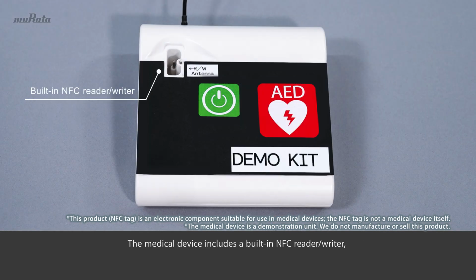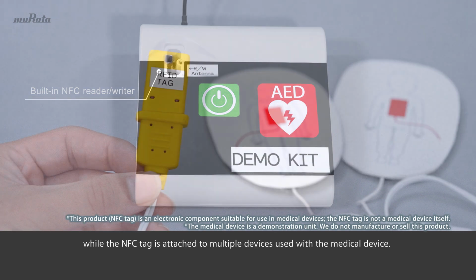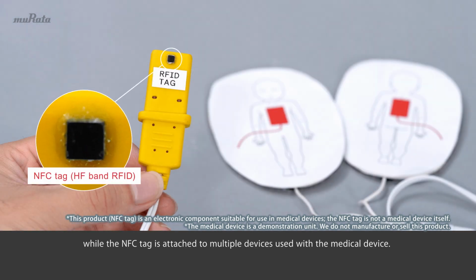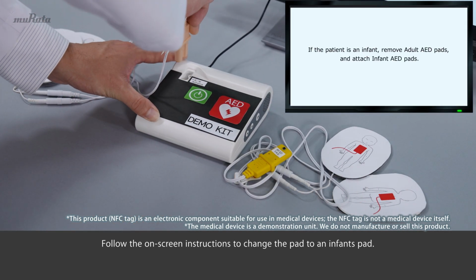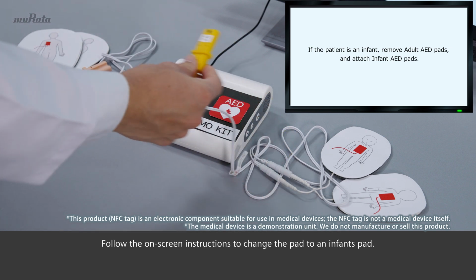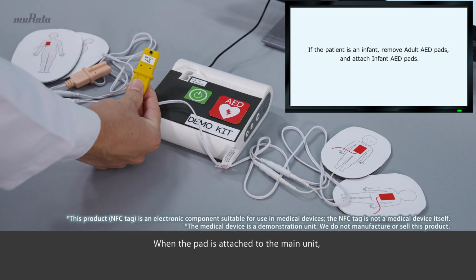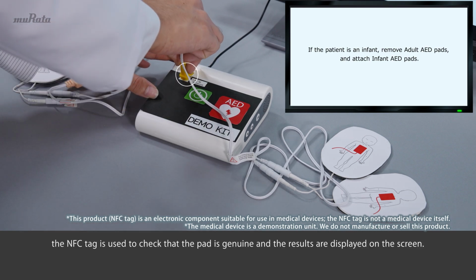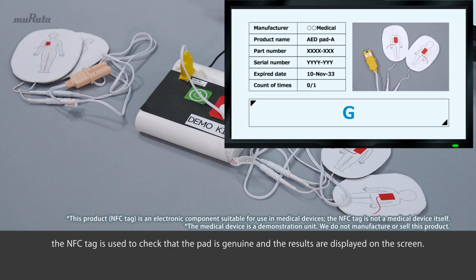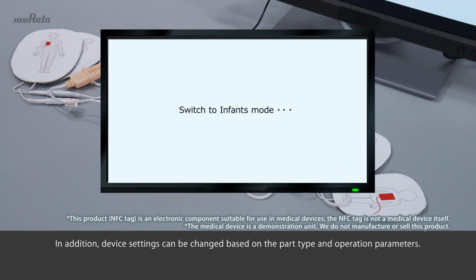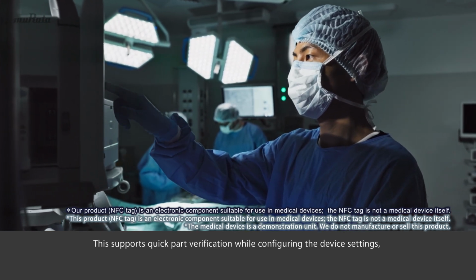The medical device includes a built-in NFC reader writer, while the NFC tag is attached to multiple devices used with the medical device. Follow the on-screen instructions to change the pad to an infant's pad. When the pad is attached to the main unit, the NFC tag is used to check that the pad is genuine and the results are displayed on the screen. In addition, device settings can be changed based on the part type and operation parameters. This supports quick part verification while configuring the device settings and can assist in procedural and operational efficiency.